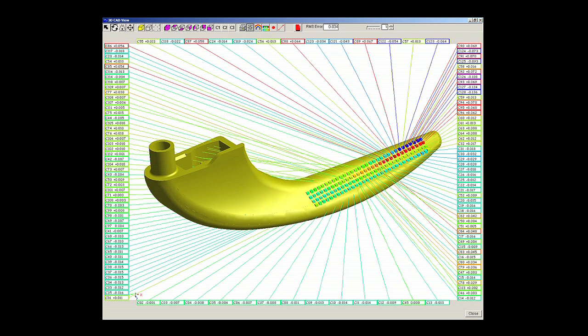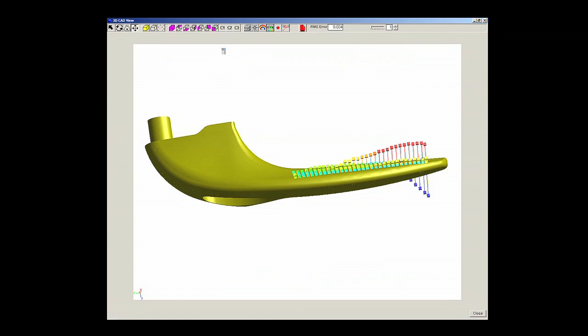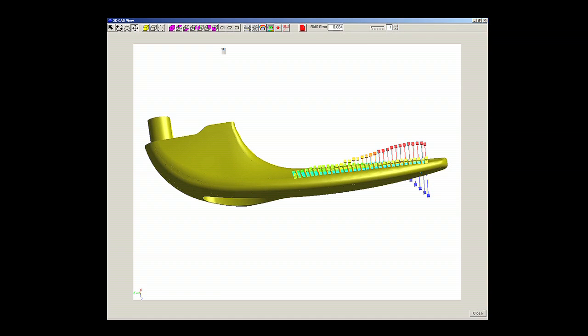Once the coordinate system is aligned to the component, random data points can be taken anywhere on the component's surface. An excellent graphic shows the point's actual position relative to the CAD model, color coding each point according to the allowable error to give an immediate visual pass-fail status.